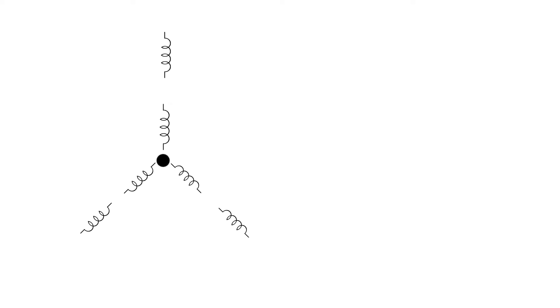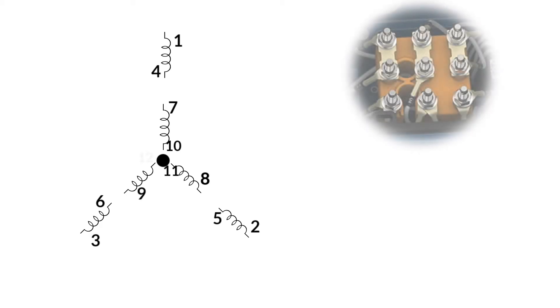This is the 9-lead star connection. The first coil is number 1 and number 4 terminal, second coil is number 2 and number 5 terminal, third coil is number 3 and number 6 terminal, fourth coil is number 7 and number 10, fifth coil is number 8 and number 11, sixth coil is number 9 and number 12. Note that number 10, number 11, and number 12 are connected to each other at neutral.